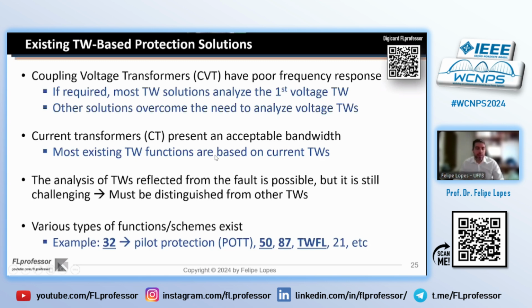Regarding current transformers, for this type of application, they have shown to present an acceptable bandwidth, and most existing traveling wave functions are based on current traveling waves. The analysis of traveling waves reflected from the faults is possible. We have seen single-ended traveling wave fault location, for instance, which detects the reflection from the fault. But this task is still challenging because it requires the reflections to be distinguished from other traveling waves.